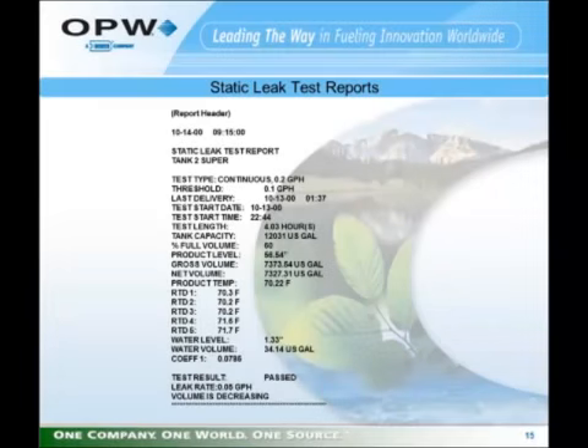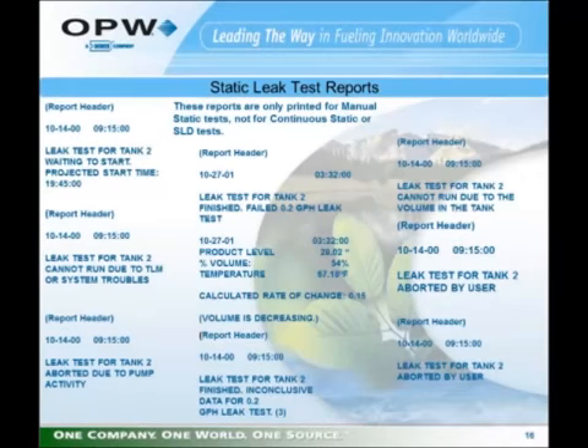A static leak test report will show you when the test began, when the test ended, all the pertinent information that you need. It'll tell you the RTD, or resistive temperature device, readings on the probe, and the water level. It will tell you a result at the bottom. The test result will be passed, failed, or inconclusive. It will give you a leak rate and tell you if that leak rate is an increasing volume or a decreasing volume in that tank during the period of the leak test. Other prints that you'll get from static leak tests are shown on this slide.